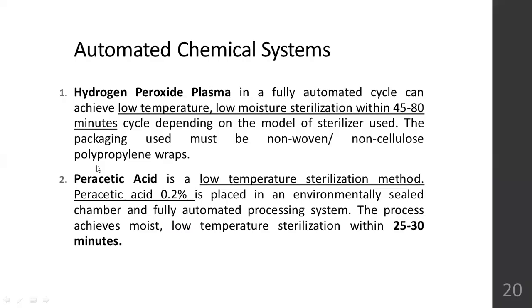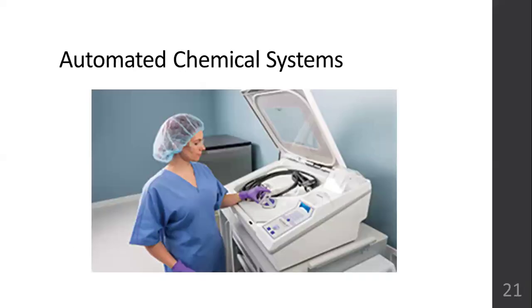If you're using the peracetic acid plasma, again, it's a low temperature sterilization because certain instruments cannot withstand high temperature, but they can tolerate low temperature. Okay, for those instruments, these kind of automated chemical system sterilizers are used. Okay, it will use peracetic acid of 0.2%. It's a high level disinfectant, sterilizer as well. And this process will require 25 to 30 minutes. So this is how it looks like.